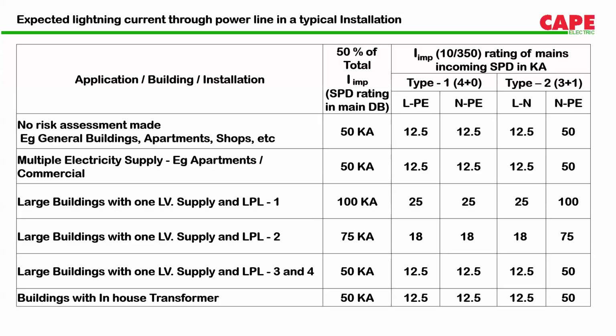class 1 plus 2 SPD, because generally the class 1 SPD waveform is a 10 by 350 microsecond waveform. That means in an impulse current, it reaches its peak value in 10 microseconds and reaches half of its crest value in the next 350 microseconds. So the total time duration is around 360 microseconds. Whereas a switching surge is around 28 microseconds. It is called an 8 by 20 microsecond surge. So the energy in a lightning surge is much more than in a switching surge. In layman's terms, we can say that a lightning surge is a bigger surge when compared to a switching surge.